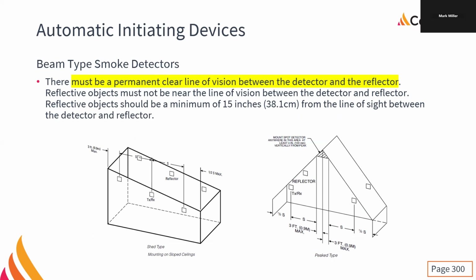The verification of them, again, quite fun because to verify, you can't just throw smoke at it. You actually have to hold up pages of dots with different intensity of dots to simulate how much smoke there is. So, it could be standing on the ground with a great big stick and a wall, a book of dots, stuff like that. The configuring of it can be really, really finicky, especially if the control unit is in a different room, so you're out of line of sight. So you might have to aim it, and you've got an apprentice on the radio telling you, "Oh, you got to go to the left or to the right, up and down," and that can be difficult if the apprentice doesn't know the difference between left and right. It can get frustrating at times.